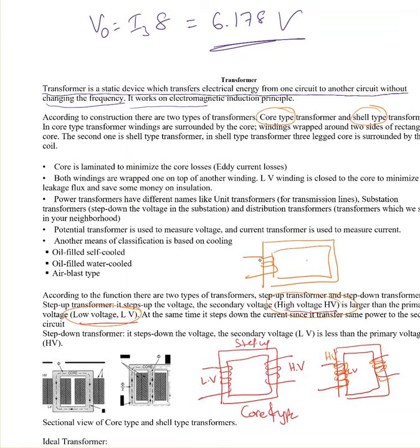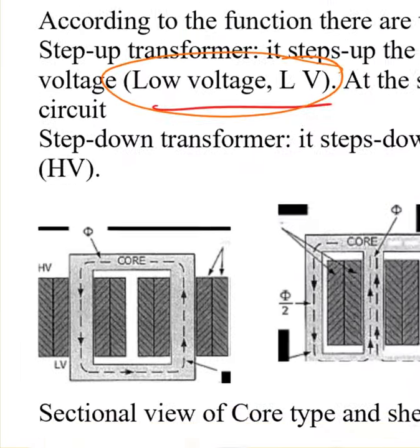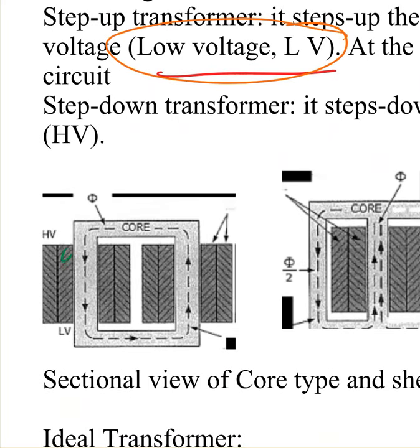Then on top of it, HV winding, half on one side and half on the other side. Both sides will have LV winding and HV winding, because it gives better magnetic coupling. So always, as you can see in this picture, there is LV winding, low voltage, and on top of it HV winding.